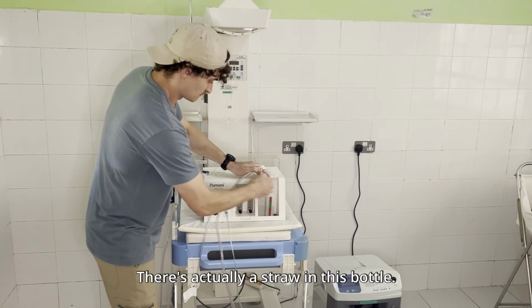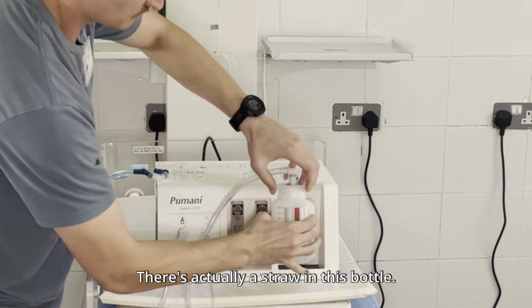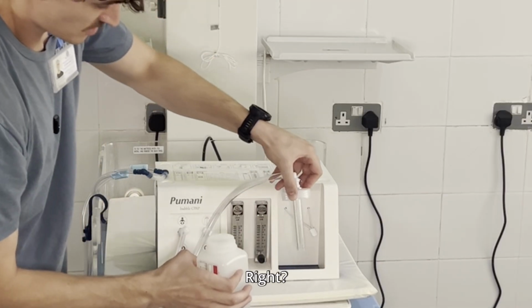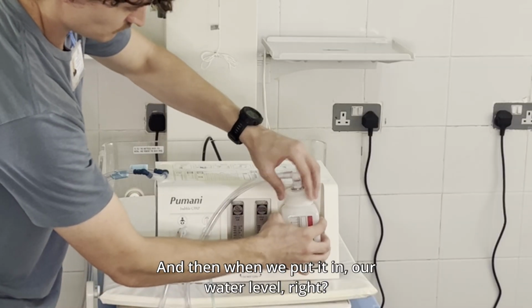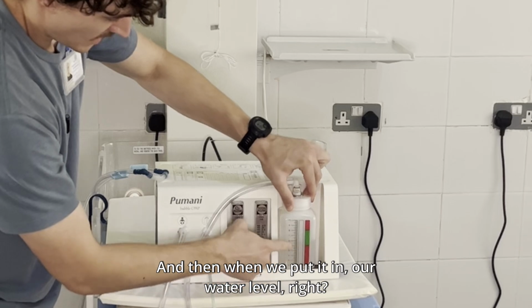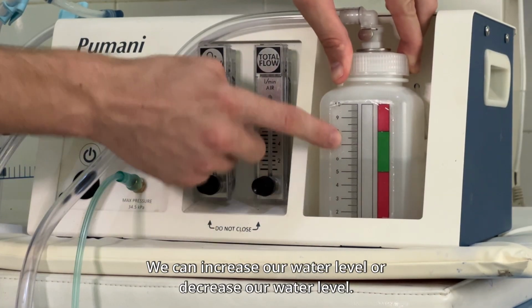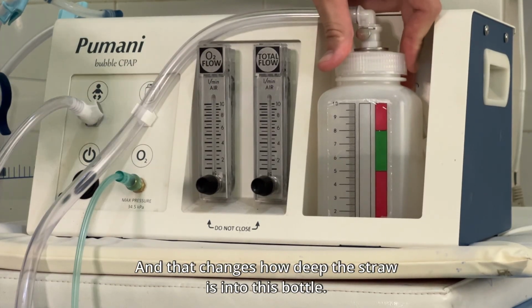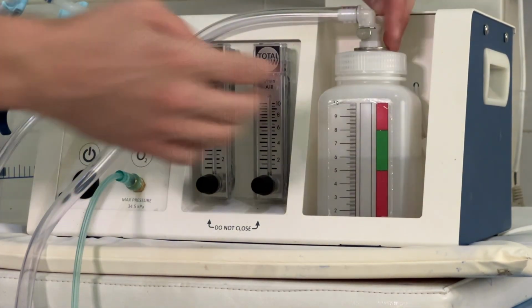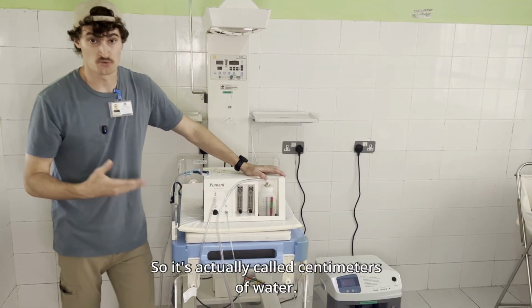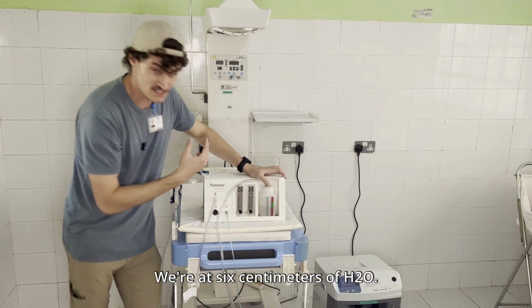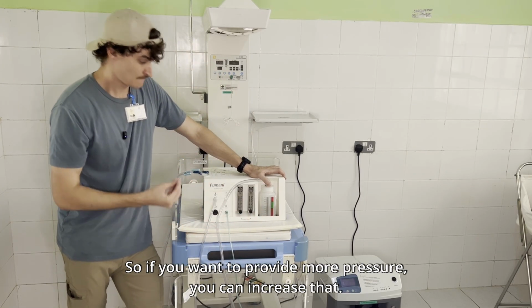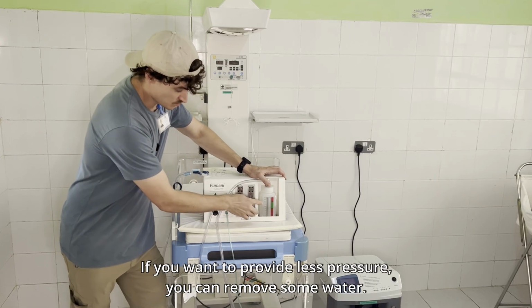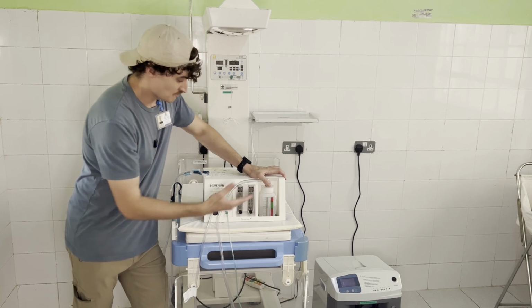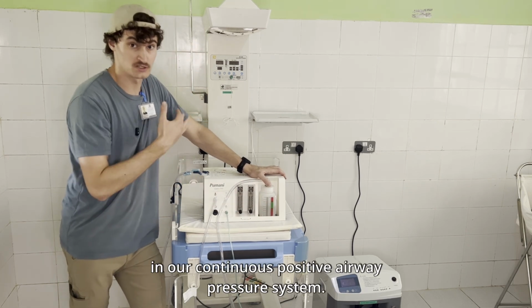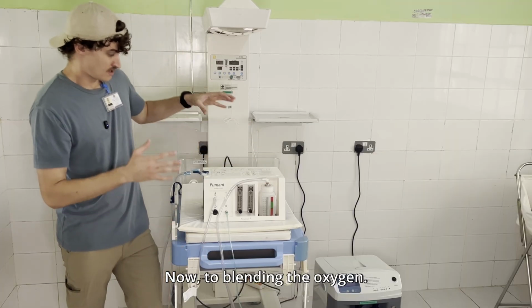I'm going to show you this right here. There's actually a straw in this bottle that you can see right here, right? So you have a straw in there, and then when we put it in, our water level, right? We can increase our water level or decrease our water level, and that changes how deep the straw is into this bottle, and that changes the pressure in our system, right? So it's actually called centimeters of water, and that is our pressure. So right now we're at 6, right? We're at 6 centimeters of H2O. So that is a measure of pressure. So if you want to provide more pressure, you can increase that. If you want to provide less pressure, you can remove some water, right? But this is ultimately what regulates the pressure in our continuous positive airway pressure system. Now, to blending the oxygen.